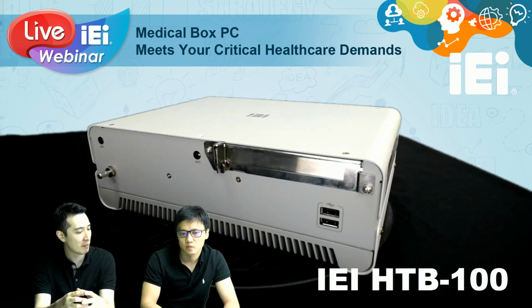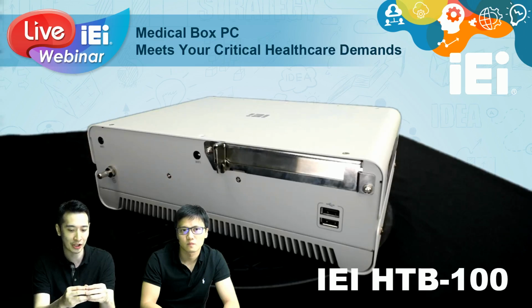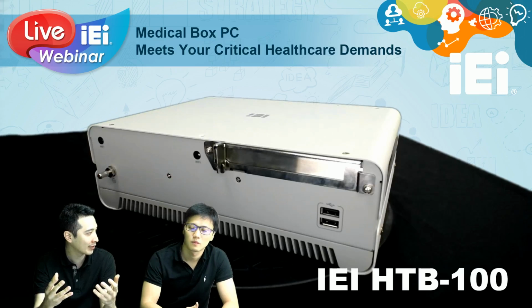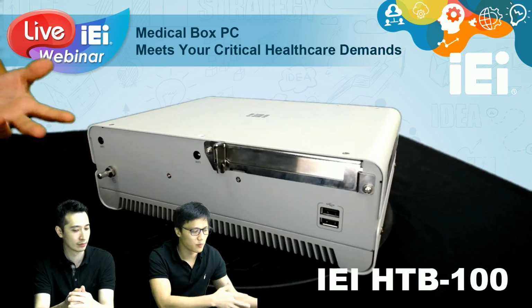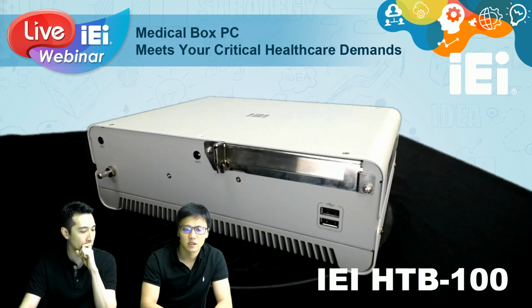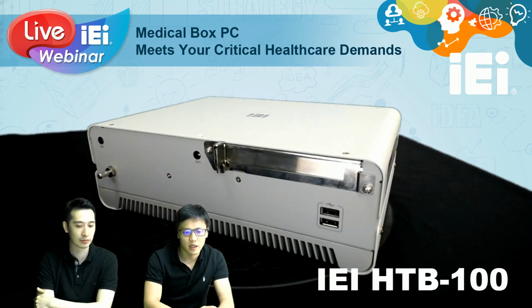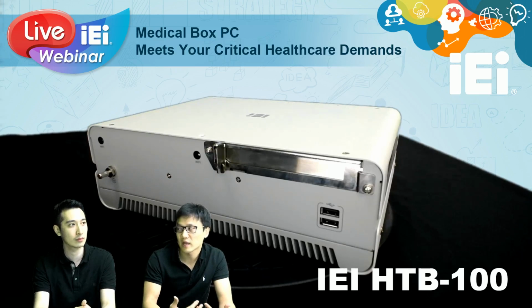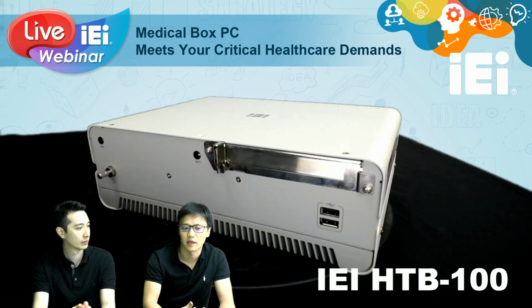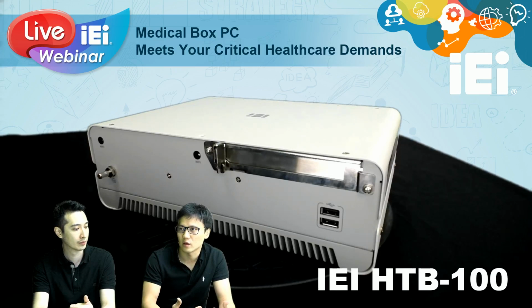Okay, you just mentioned medical certification. We also know that medical certification IEC 60601 has just released the 4th version. So what are the impacts globally? Okay, in the beginning of designing our product, we follow the safety compliance, normally in the US market or the EU market. Something like the IEC 60601-1, as you mentioned. In the US market, they enforce medical products to pass those safety compliance starting from April 1st, 2017, and in the EU market, starting from January 1st, 2018.